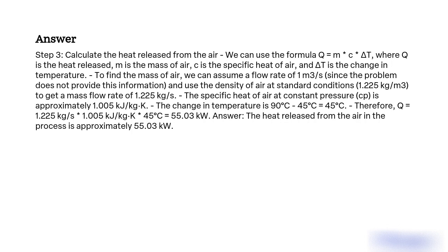The specific heat of air at constant pressure cp is approximately 1.005 kJ/kg·K. The change in temperature is 90°C - 45°C = 45°C. Therefore, Q = 1.225 kg/s × 1.005 kJ/kg·K × 45°C = 55.03 kW. Answer: The heat released from the air in the process is approximately 55.03 kW.